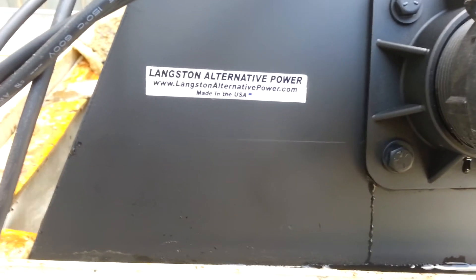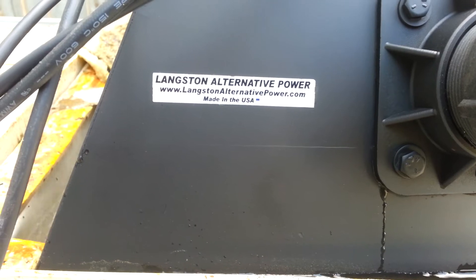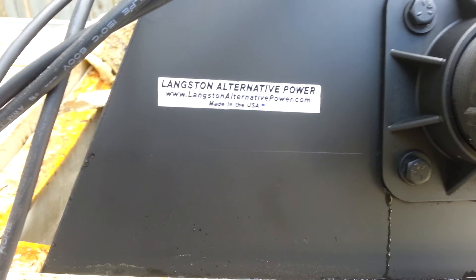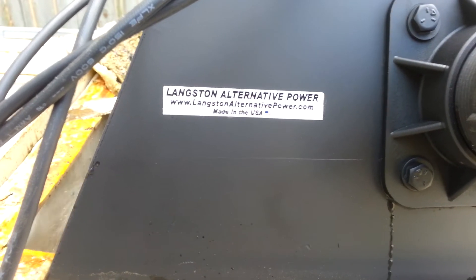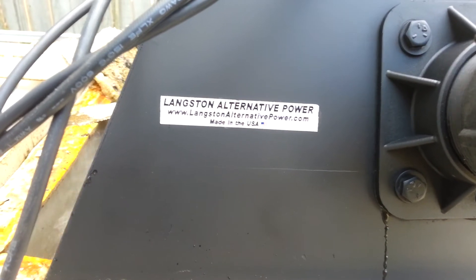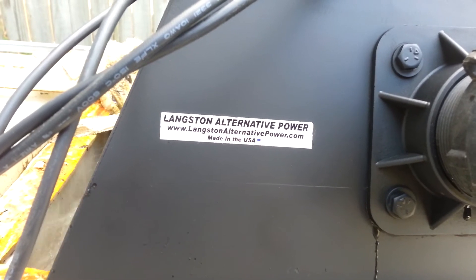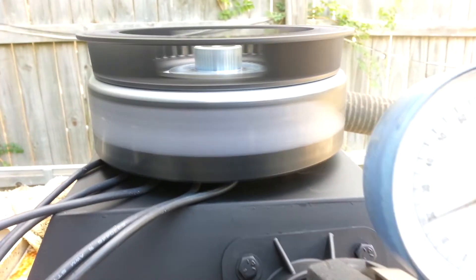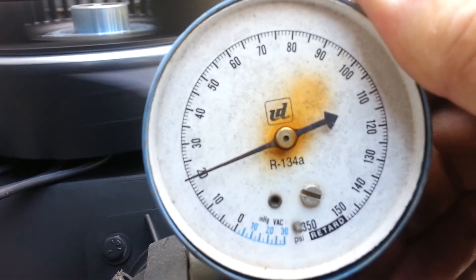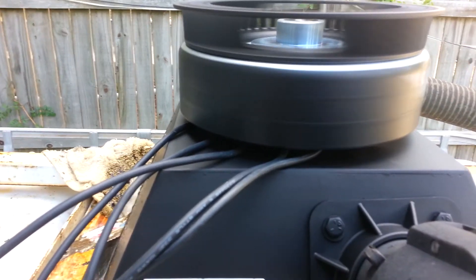Hey, this is Spencer at Langston's Alternative Power. This is a little demo of a Turgo Hydro Generator — a three-phase permanent magnet alternator — now running three-phase AC high voltage to a Sunny Boy grid-feeding inverter at 20 psi, 1700 RPM. This is all under load.